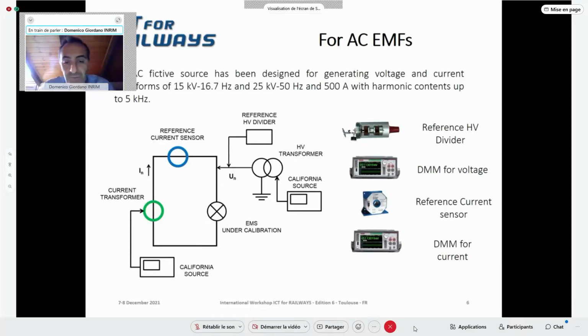With this calibration facility, we can perform calibration of the whole measurement chain, involving a transducer and the energy calculation function. We need a reference divider for voltage measurement and a reference sensor for current measurement in order to know with high accuracy the signals we are applying. Thanks to the low voltage generators, it's possible to apply not only sine waveforms but even waveforms with distortions.